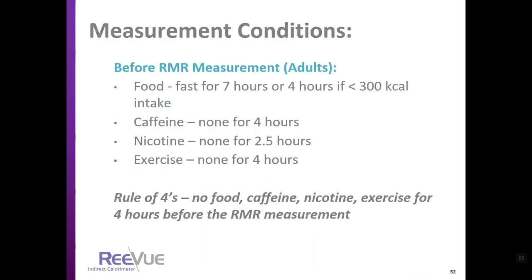Measurement conditions are very important to assure accuracy. Before the resting metabolic rate measurement for adults, food should be eliminated — a fast of 7 hours, or 4 hours if a small meal was taken in. Caffeine: none for 4 hours. Nicotine: none for 2.5 hours. Exercise: none for 4 hours. The rule of thumb is no food, caffeine, nicotine, or exercise for 4 hours before the RMR measurement.